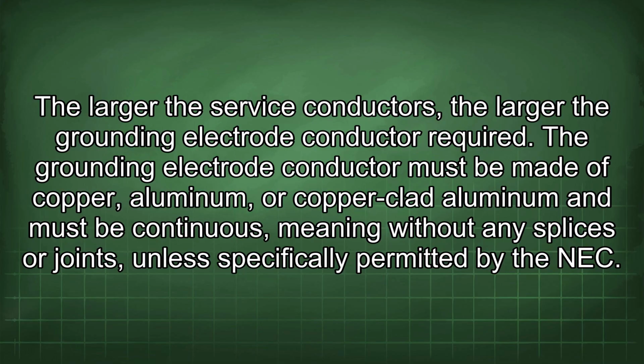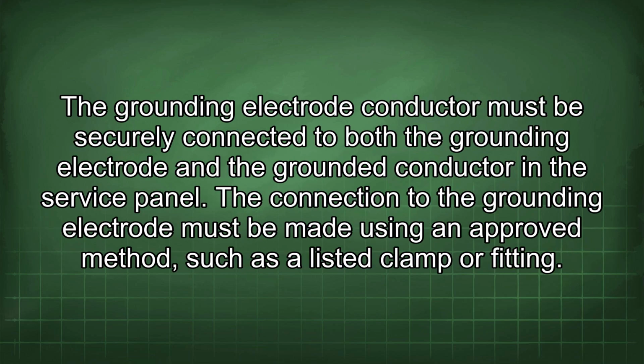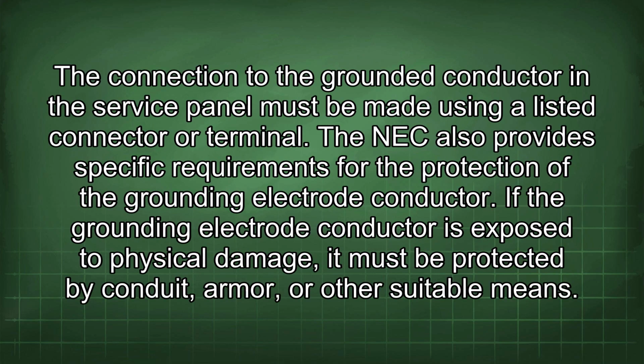The grounding electrode conductor must be made of copper, aluminum, or copper-clad aluminum and must be continuous, meaning without any splices or joints, unless specifically permitted by the NEC. The grounding electrode conductor must be securely connected to both the grounding electrode and the grounded conductor in the service panel. The connection to the grounding electrode must be made using an approved method, such as a listed clamp or fitting. The connection to the grounded conductor in the service panel must be made using a listed connector or terminal.